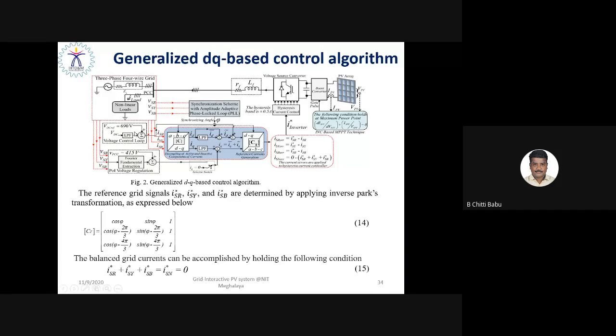So the DC link voltage is set with a reference of 690 volt. That will be compared with the actual DC link voltage. Then the error will be given to generate the ID component reference in the loop. And moreover, the three-phase AC current is transformed into ID, IQ with the help of the ABC to DQ transformation. Then we have a low-pass filter to filter out the double frequency oscillation. Finally, you are able to generate ID as well as IQ star, right? And on the voltage loop, your three-phase AC voltage will be converted into two-phase voltage values. So that will generate the IQ component.